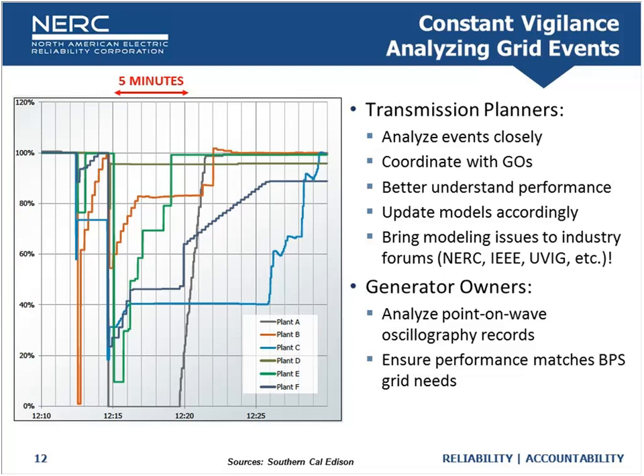From a generator standpoint, we're strongly advocating point-on-wave oscillography records either within the plant or at the point of interconnection, because we need to know what's going on at each individual inverter and how the overall plant is behaving. We need very high-resolution data. Some things like momentary cessation are happening in the couple-cycle range, so even PMU data can wash out some of the momentary cessation issues we want to see for large disturbance verification. Point-on-wave oscillography data is really what we're advocating.